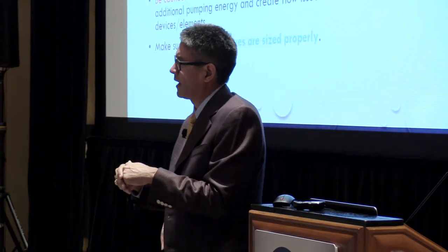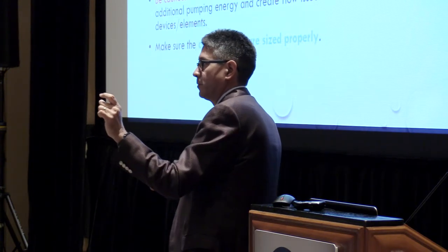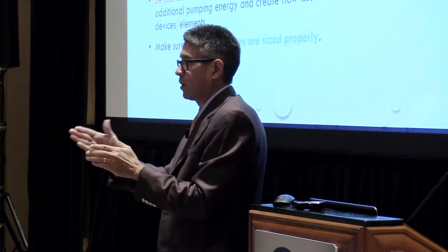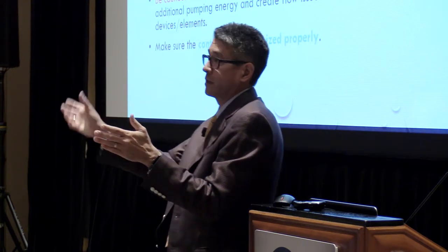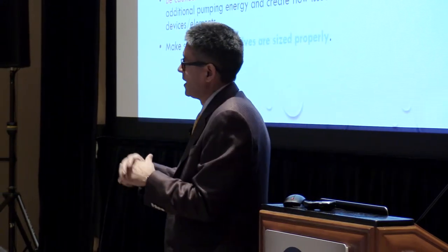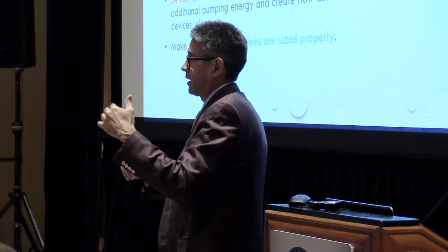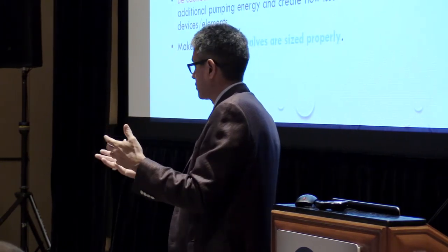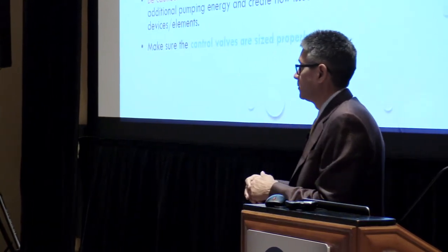So if you start hearing a loud chatter noise and you got control valves, it's really not that spring chattering like a lot of people think. It's that control valve and the water pulsing between the automatic flow limiting device and the control valve. So yes. You have to be very careful with that, and you have to look and say, what is my anticipated pressure there? So which auto flow selection should I have? Should I have a 5 to 60 or a 2 to 32? And then even still, you might have that issue come up. So great question.